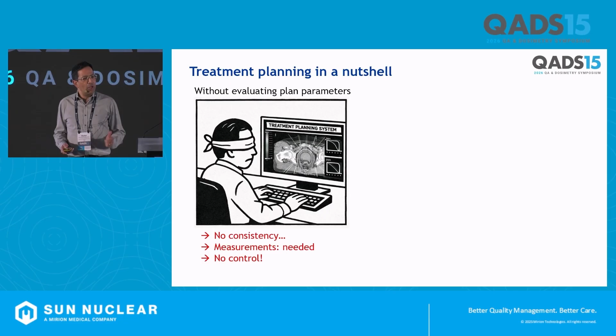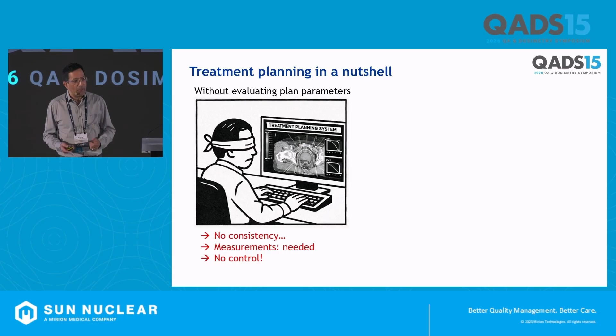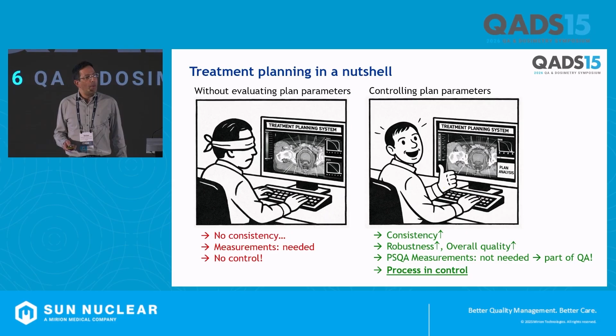So just to illustrate it with a couple of images, you can do treatment planning without evaluating plan parameters, just taking a look at the dose distribution, at the dose on the screen. But then there's no consistency in your treatment plans. So you're not controlling that. So that's when, of course, you need measurements, pre-treatment measurements of all the plans, because you're not in control. Or you can control the plan parameters. Then you have consistency, you reduce variability, you improve robustness, quality, and you don't really need PSQA measurements of all plans anymore, because that's part of QA. You move that to QA, which is, of course, much more efficient, because then the process is in control.